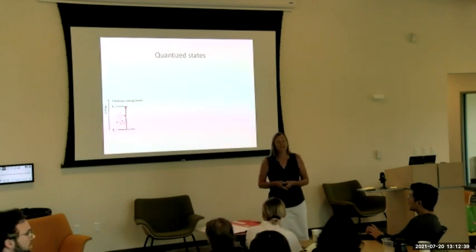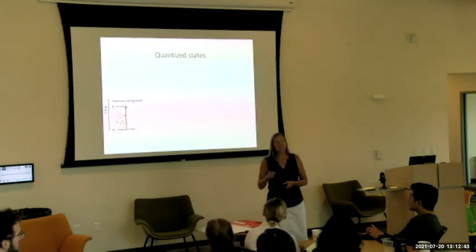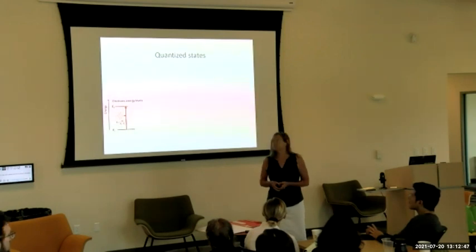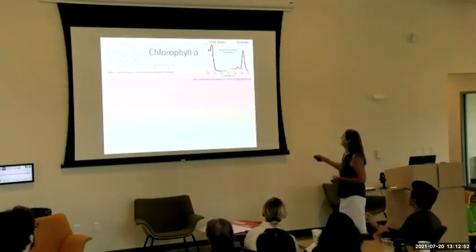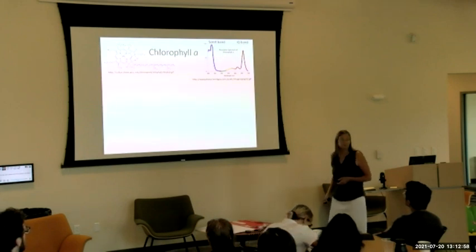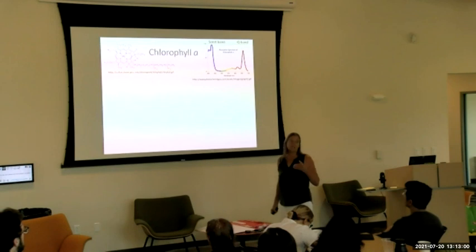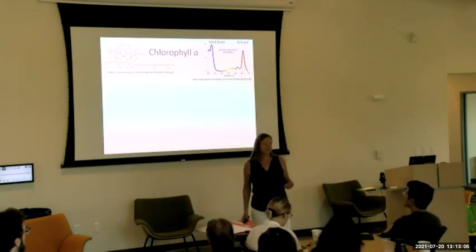Who would have thought? So you're actually exciting an accessory pigment that's in the cell that passes its energy to chlorophyll, and then chlorophyll fluoresces. But it's a really important point to recognize that. I'm glad you brought that up. Yes, you don't want to excite here. So most of our fluorometers excite at 470, which is right here. So they're actually very bad chlorophyll fluorometers. They're very good phytoplankton fluorometers.